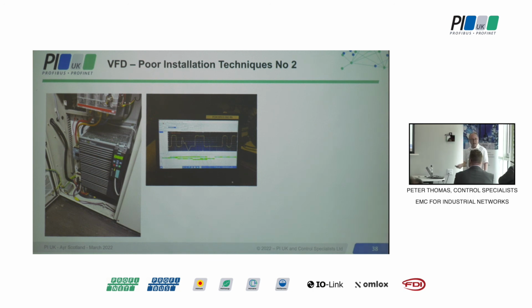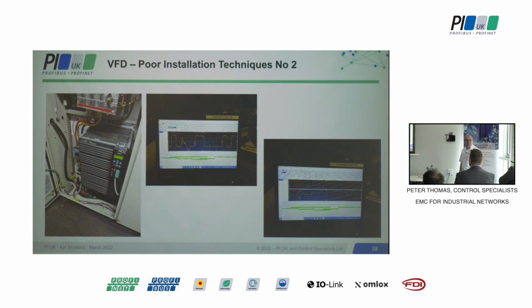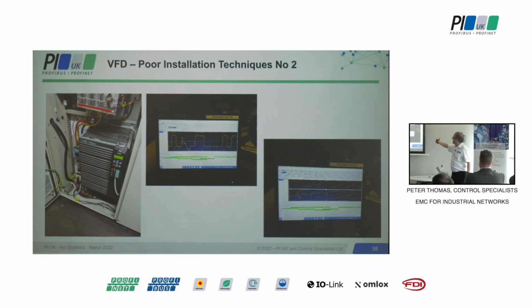And when you do that, it's always a good way of saying this is EMC. Look what we see on the individual ones. The telltale sign here, if you can just see on the right, it just returns to normal ones and offs. And with RS485, if it goes up on one line, it goes down on the other. There's a mirror image. Whereas here, they're clearly in phase. And that's 100% certainty. This is EMC.